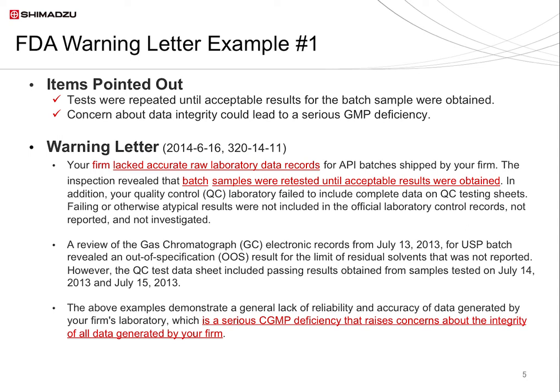I would now like to describe the background to these observations by going through three actual FDA warning letters. The first example is a letter dated June 16, 2014. The FDA noted batch samples were retested until an acceptable result was obtained. An analysis was being repeated multiple times. The operator watched the chromatogram as data was displayed, and if it did not meet their expectations, they pressed a button that stopped the ongoing analysis and then repeated the analysis until the desired result was obtained, with only the best result being used. The FDA commented that any data obtained in this way could not really be trusted.